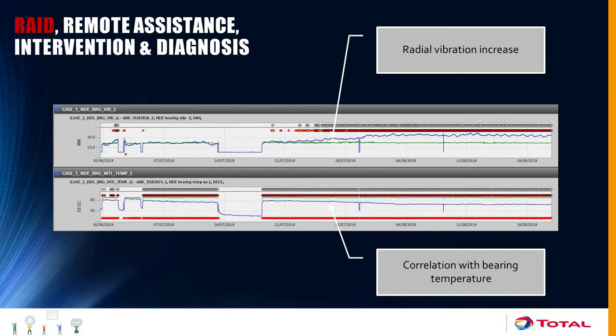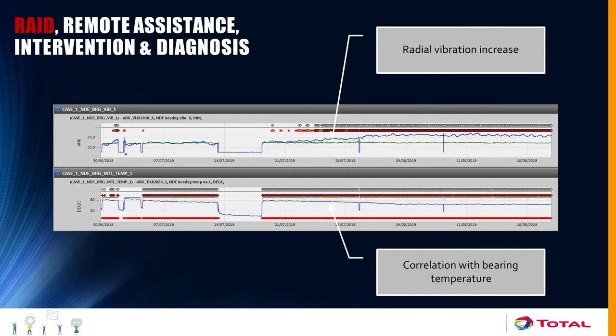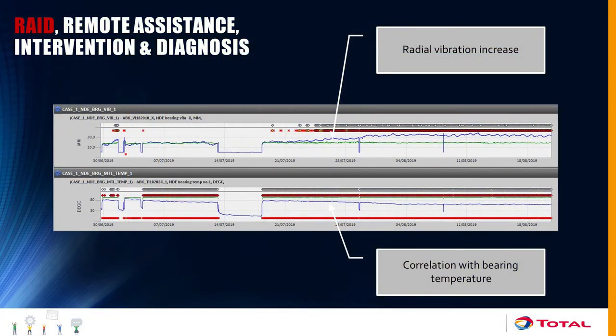This next case is not an immediate failure, but I find it very valuable. We can see an increase in vibration level on the upper trend, but the problem is not coming from a direct bearing failure. This case illustrates — and we use it as a training slide — the direct correlations we are able to perform within SmartSignal. The vibration increase is linked to the lube oil temperature. Physically, there is an impact between lube oil temperature and vibration level, so we use SmartSignal to show these correlations and contribute to a proper diagnosis.